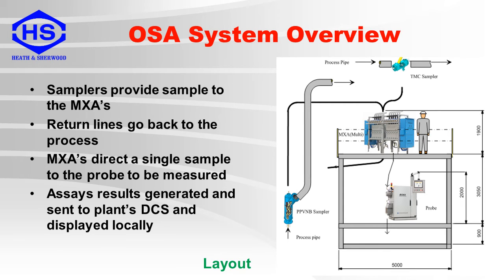Here is how a sampling system may be used for process control using an on-stream analyzer. The samplers situated around the plant provide a continuous or on-demand flow of slurry to the multiplexers. The samplers can be either metallurgical or process controlled types. The main sample flow rejects are returned back to the process. When the analyzer is ready, the process sample is directed through a flow cell for measurement, and the analyzer system then outputs the results to the plant control system.